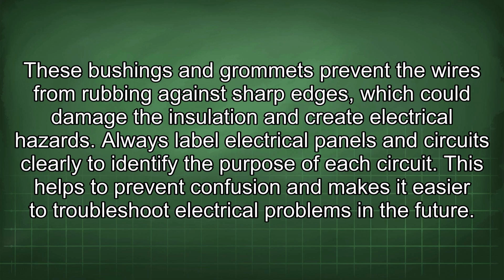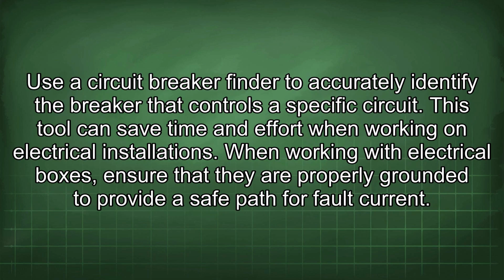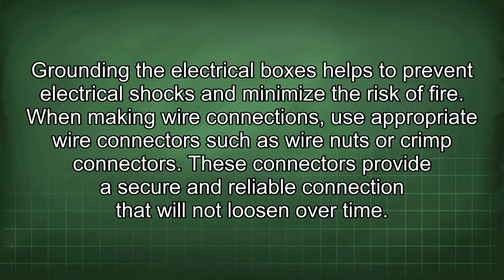Always label electrical panels and circuits clearly to identify the purpose of each circuit. This helps to prevent confusion and makes it easier to troubleshoot electrical problems in the future. Use a circuit breaker finder to accurately identify the breaker that controls a specific circuit. This tool can save time and effort when working on electrical installations. When working with electrical boxes, ensure that they are properly grounded to provide a safe path for fault current. Grounding the electrical boxes helps to prevent electrical shocks and minimize the risk of fire.